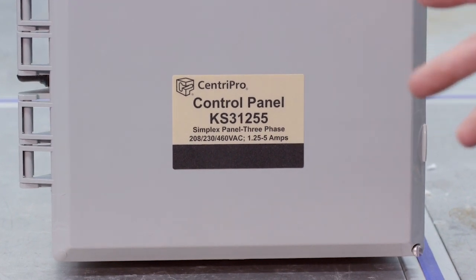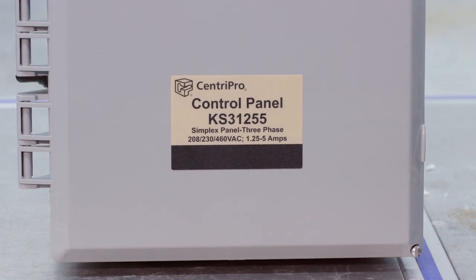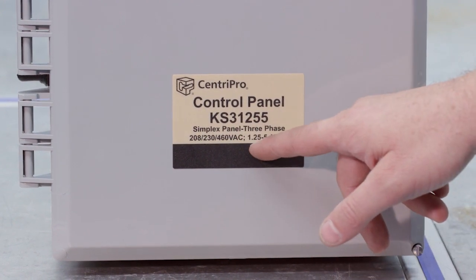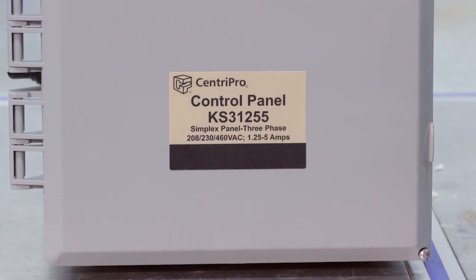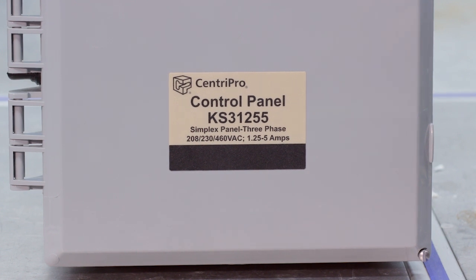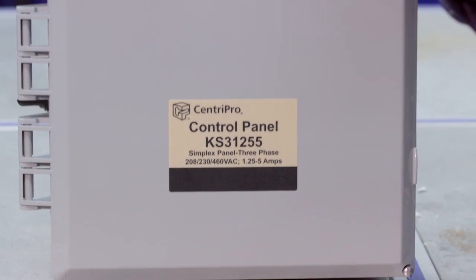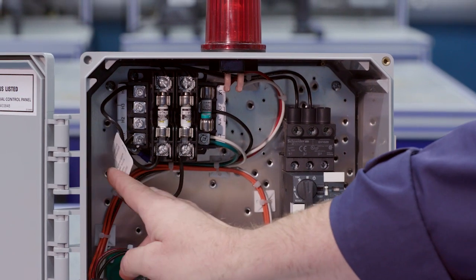We're looking at the control panel KS31255, simplex three-phase, 1.25 to 5 amps, and again it's multi-voltage. We've got to make sure that we wire this, and it's only going to be one wire to the proper voltage, making sure it's equal to the supply voltage, which is equal to the pump voltage.